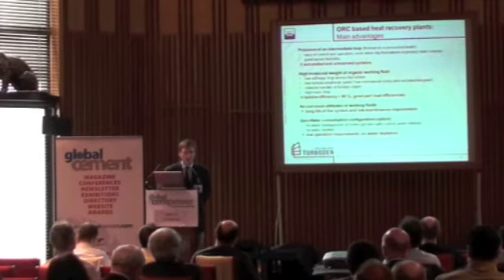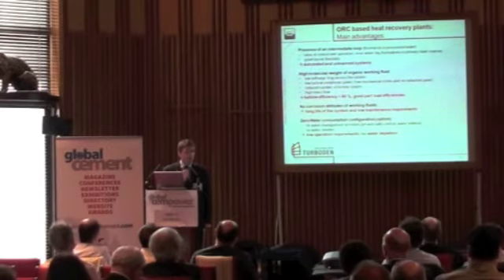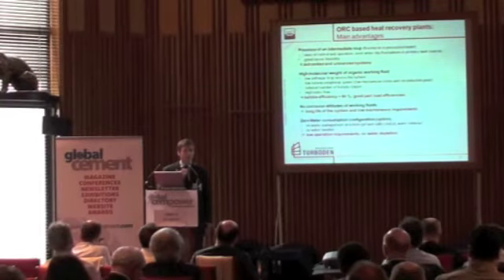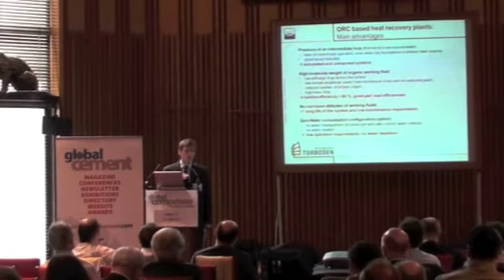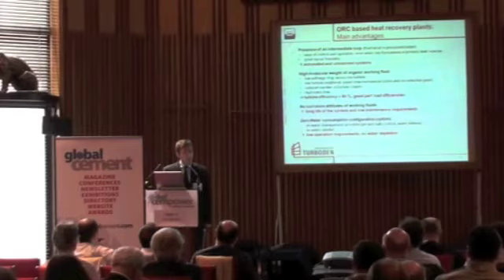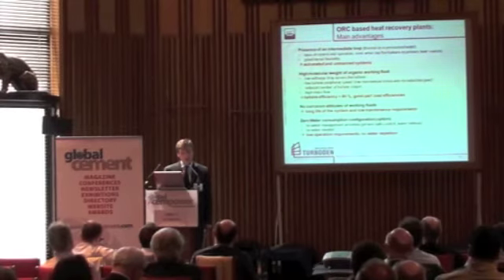I don't know how many of you can directly relate enthalpy drop to the effect. Enthalpy drop means a lower number of stages, so an easier turbine. Instead of making 10 or 15 stages, we just make 2, 3, 4 stages. Also, lower turbine peripheral speed. A steam turbine, depending on the size and the specific technical selection, typically rotates at 10,000 RPM. Thanks to the low enthalpy drop, we have turbines rotating at 3,000 RPM. So it is, on one side, mechanically easier to build. On the other side, it can be directly coupled to a two-pole generator, so it brings a double advantage.